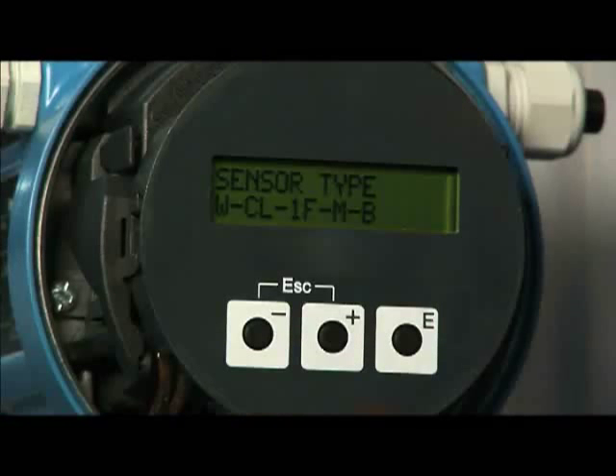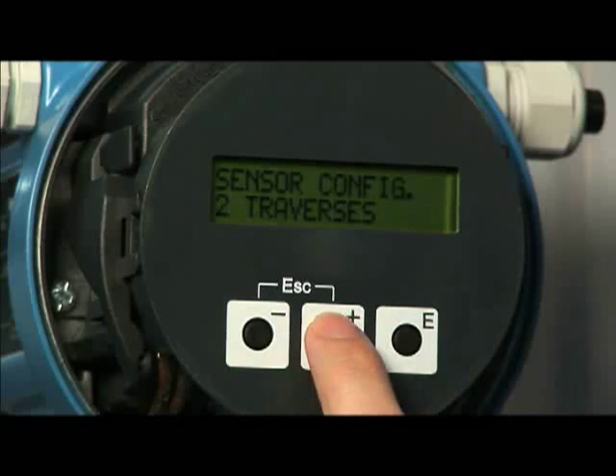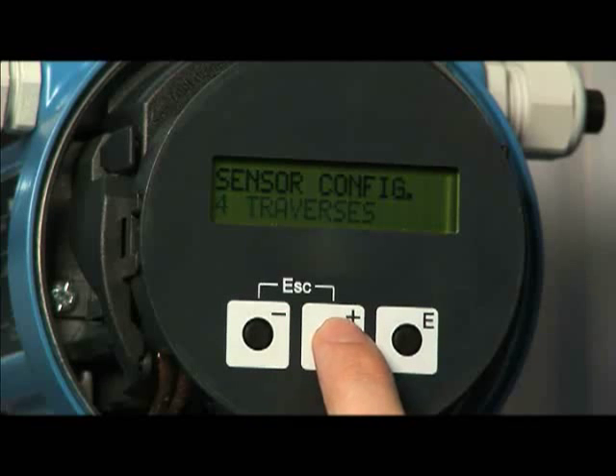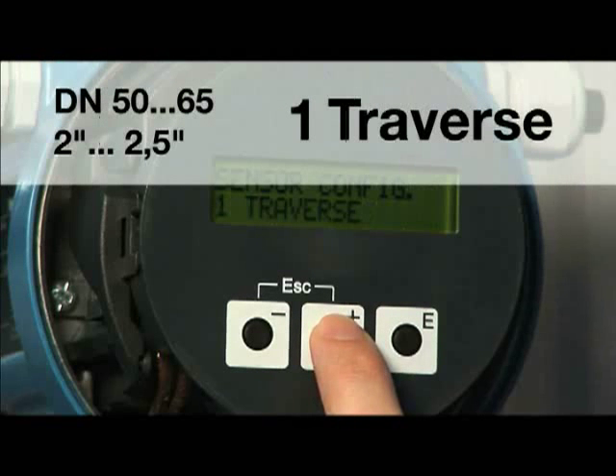The transmitter will prompt the number of traverses. The number of traverses determines if the sensors are to be mounted on opposite sides of the pipe, in a one traverse installation, or on the same side of the pipe, in a two traverse installation.